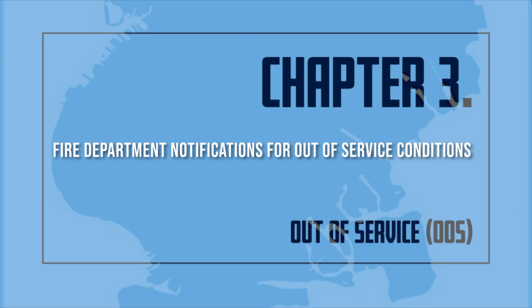D. When the certificate of fitness holder observes a minor defect or other condition not presenting a serious safety hazard, he or she shall report the defect or condition to the owner, and if the defect or condition is not corrected within 30 days, it shall be deemed to be an impairment and reported in writing to the fire department. Fire Code 901.7.5.